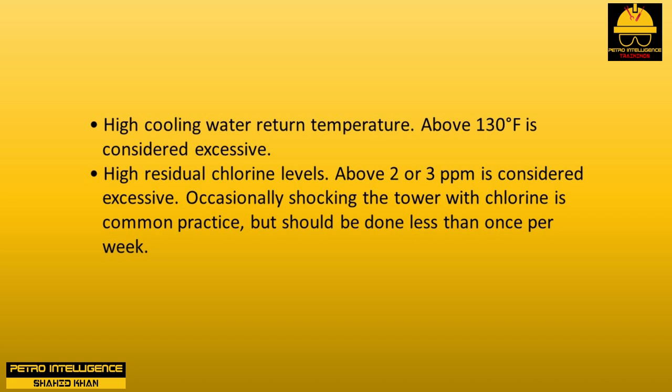Above 2 or 3 ppm residual chlorine is considered excessive. Occasionally shocking the tower with chlorine is common practice, but should be done less than once per week.